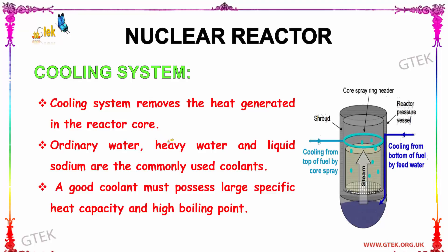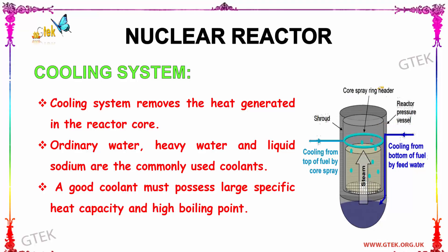Now let us see about the cooling system. The cooling system removes the heat generated in the reactor core. Ordinary water, heavy water, and liquid sodium are the commonly used coolants. A good coolant must possess large specific heat capacity and high boiling point. The cooling system cools the fuel from the top by core spray and from the bottom by feed water, and includes a shroud, reactor pressure vessel, and core spray ring header.